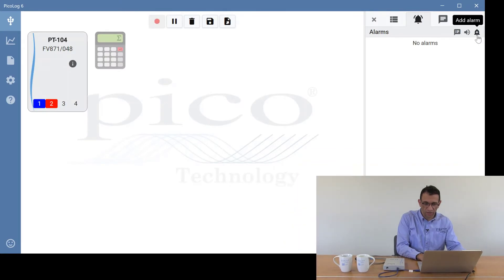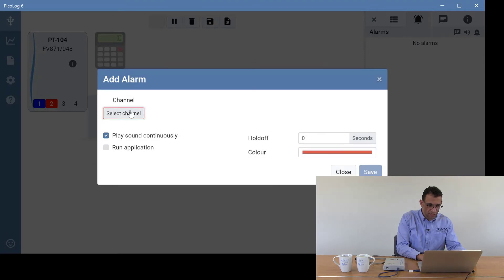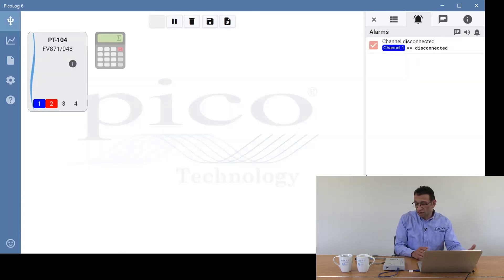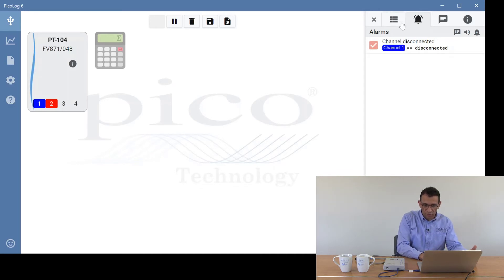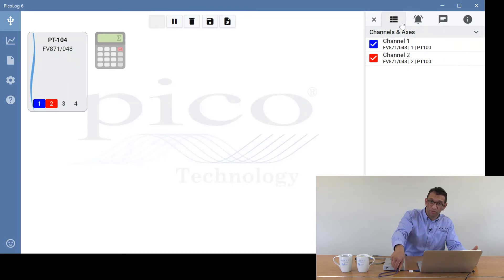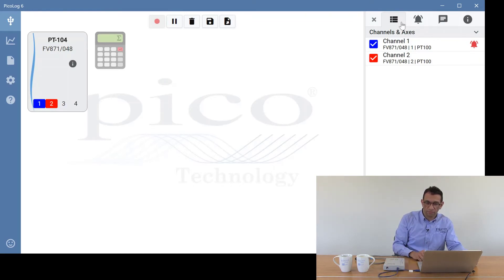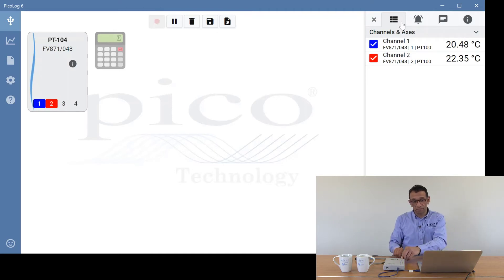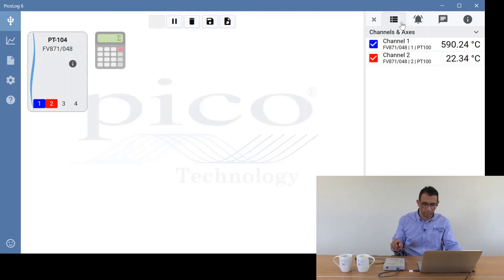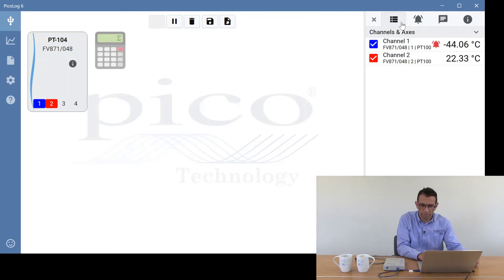The next alarm is the channel disconnect alarm. Clicking add alarm and going to channel disconnected, we select the channel we're interested in — channel one — and click save. As the name implies, when the channel is disconnected it will alarm. Going to the channel axis menu and unplugging the unit, you can see it alarming. Plugging it back in again it stops alarming. You can also trigger this by unplugging the temperature sensor itself, and plugging it back in stops the alarm.